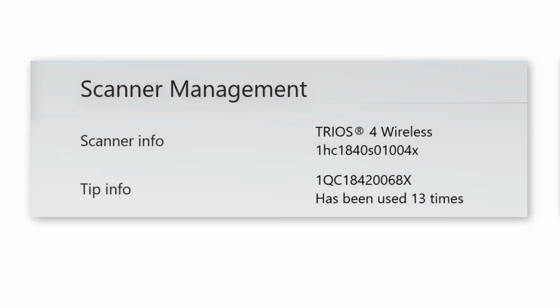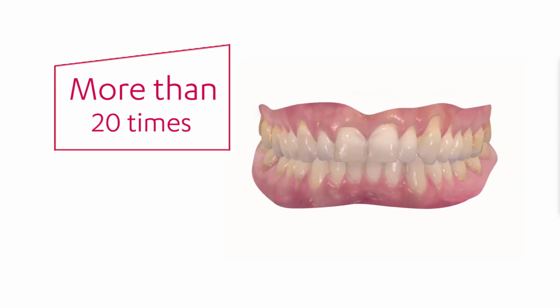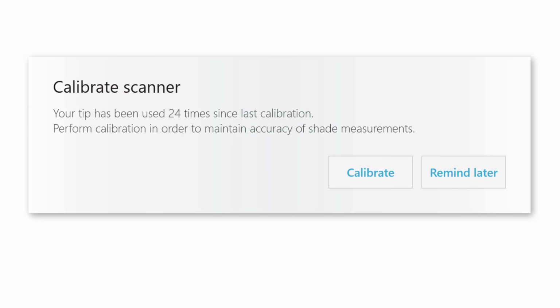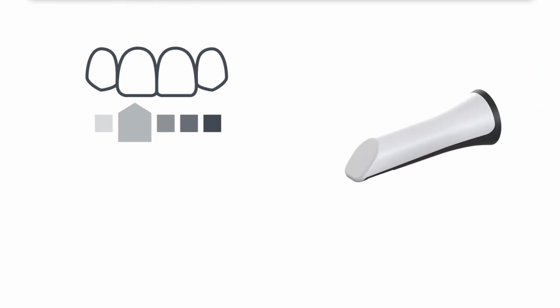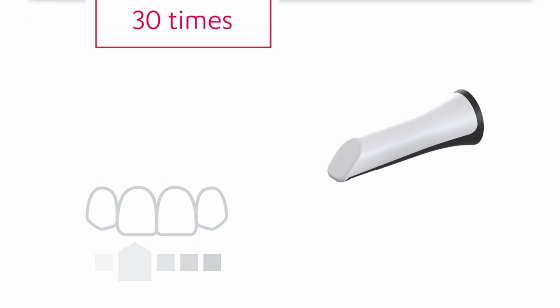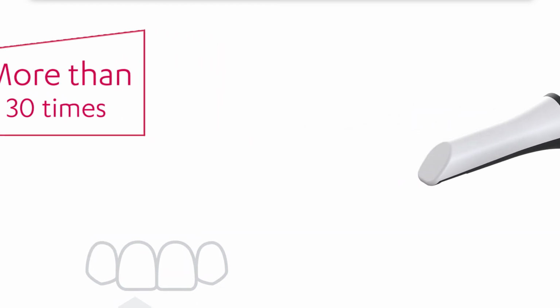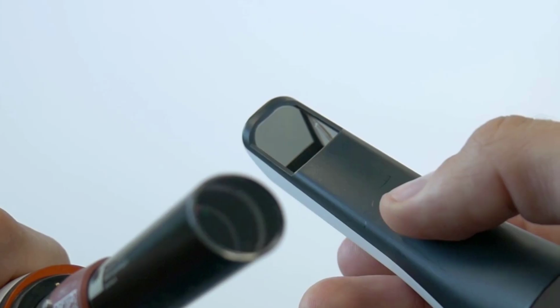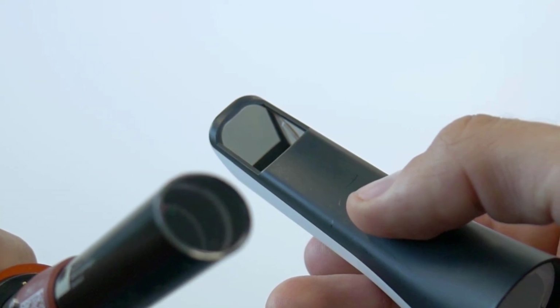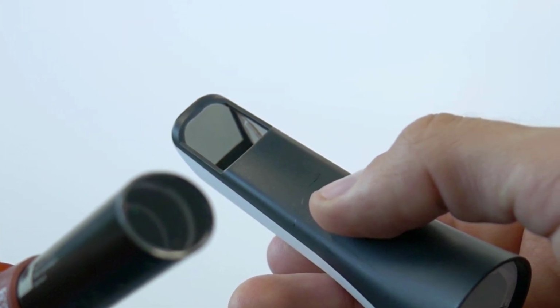The number of scans taken with a tip is registered in settings, and when more than 20 scans have been taken, a pop-up will inform you about the need for calibration. Shade measurement with a given tip will be disabled if the tip has been used more than 30 times. The scanner should also be calibrated after it has been moved, shaken, or sustained a wide range of temperature changes. If the mirror looks dirty or hazy, it's a good idea to clean it properly and calibrate it.